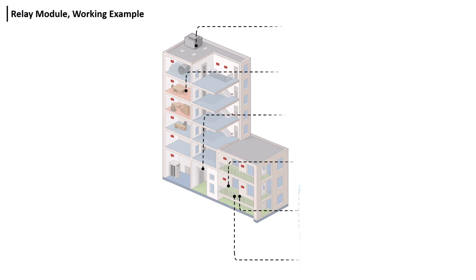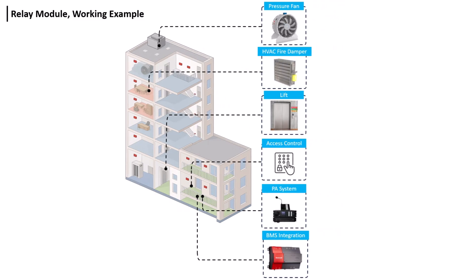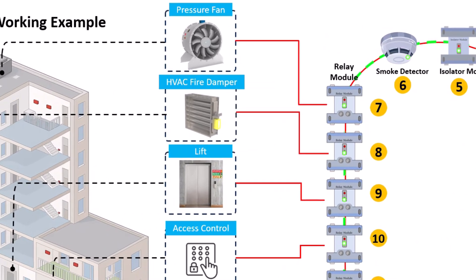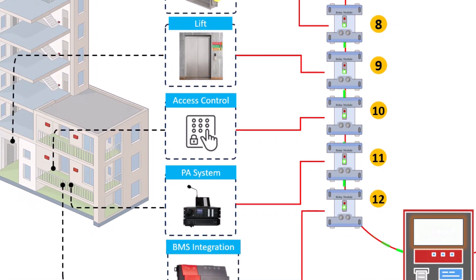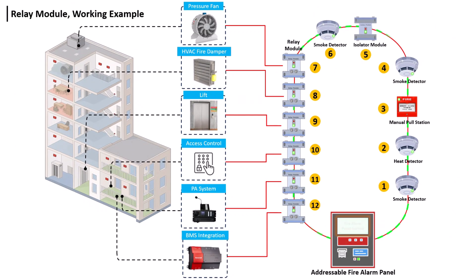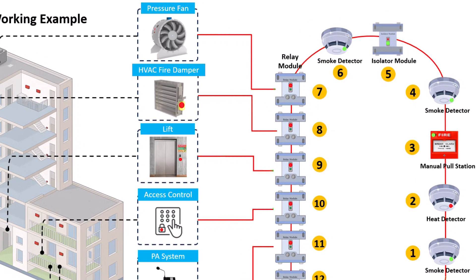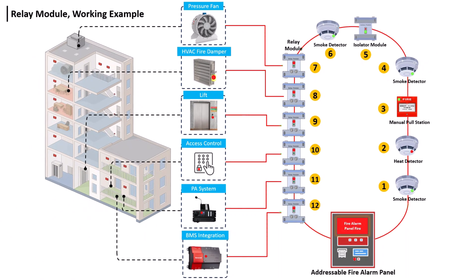Buildings have lifts, exhaust fans, PA systems, and BMS systems. When a fire event occurs, these devices need to be controlled or turned on or off, so a relay module is used to connect third-party devices with the addressable fire alarm. In this example, the relay module is connected with the lift panel, PA system, and exhaust fan controller. Since the relay module is only for triggering, we cannot directly apply any load to it. When a fire event occurs, the detector sends a signal to the fire alarm panel, which then sends a signal to the relay module, activating the lift, PA system, and exhaust fan.